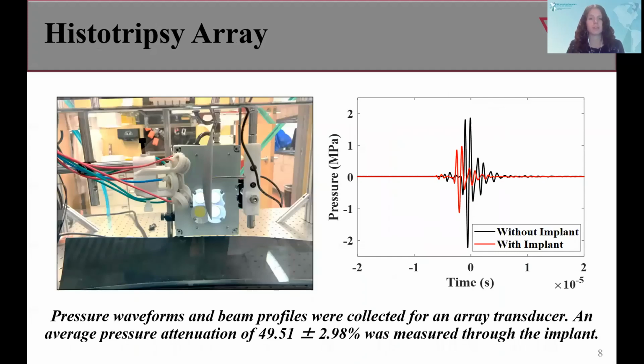Pressure waveforms and beam profiles were also collected for an 8-element, 1 megahertz histotripsy array transducer designed for brain tumor ablation. An average pressure attenuation of 49.5% was measured through the implant as shown on the right, much higher than that reported by Prada et al. at 1 megahertz, but within the range measured in the study for single-element transducers at different angles.